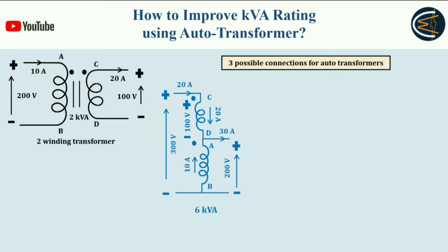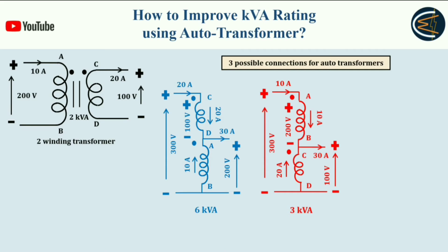This is one possible connection. Now let's see another connection. Here I just interchange the positions of the windings — AB winding is placed differently and CD winding is placed here. Similarly, 300 volts is applied on the primary side, but here the secondary side has 100 volts, and the current rating is also not violated. If you calculate, you will get 3 KVA.